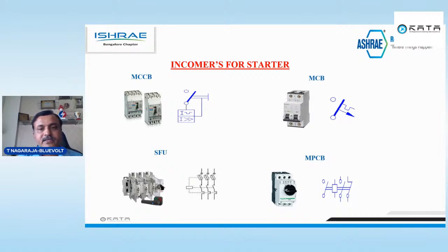But whereas your MCCB, MCB and MPCBs will not be like that, because those are thermal trip. It will take time, 60 to 90 seconds. Your thermal element should get heated up, then only it will trip. So you have to select a contactor accordingly. It should hold the short circuit or overload for such time. That's why in your type 2 coordination, when you compare the switch fuse, where switches are used along with the fuse, the rating will be lesser, and whenever using MCCB, MCB and MPCB, your rating will be different.